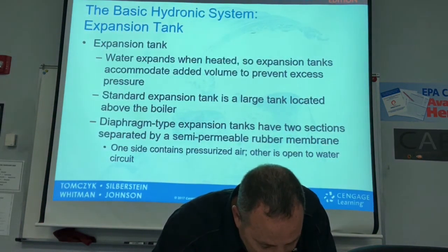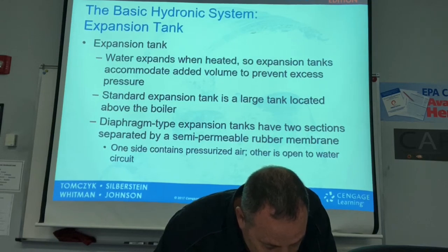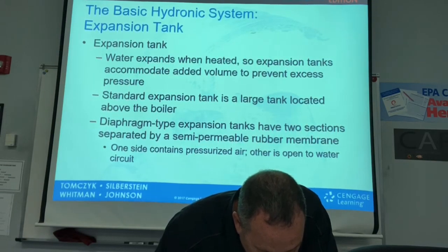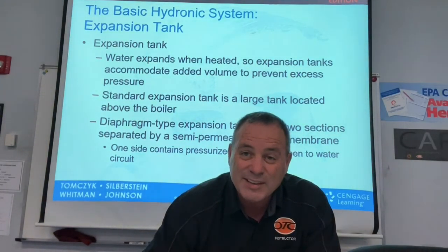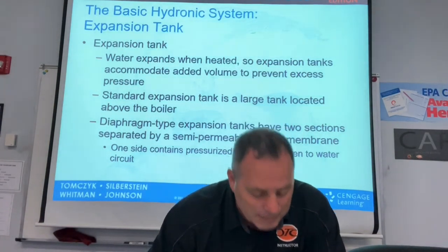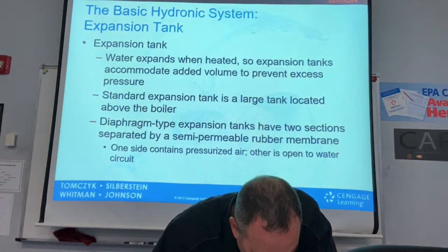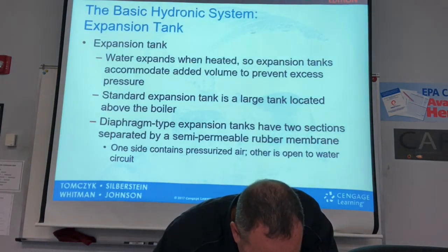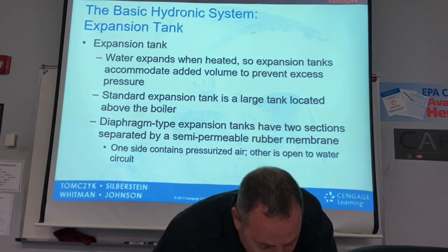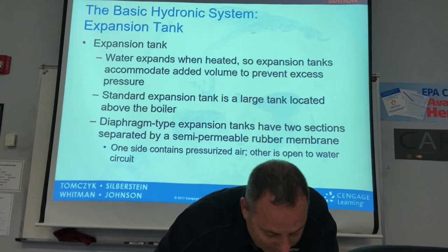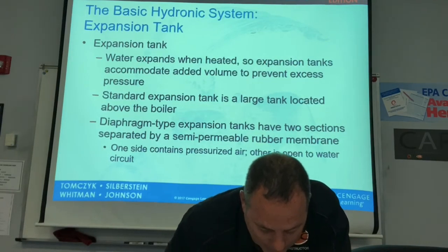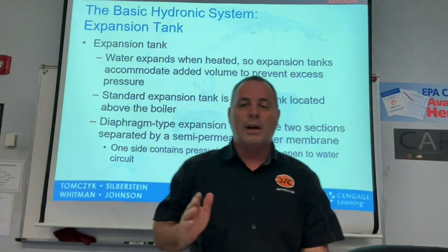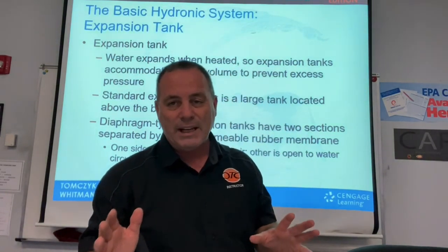As water is heated it expands. Since the system is totally closed with no inlet or outlet, the pressure in the piping circuit increases as it heats up. The excess pressure will cause the pressure relief valve to open every time — except when you install a compression or expansion tank.